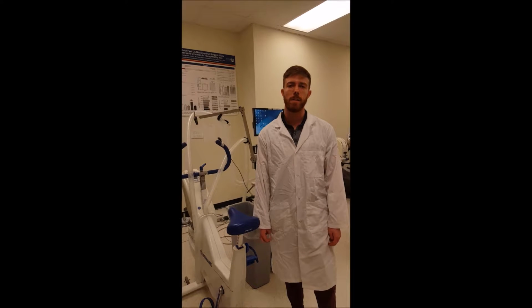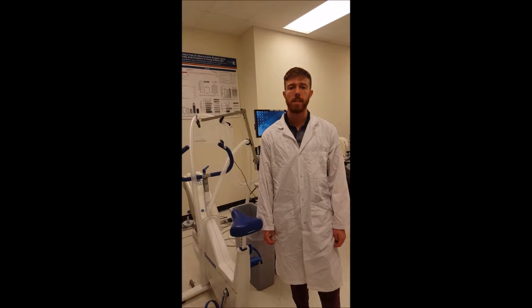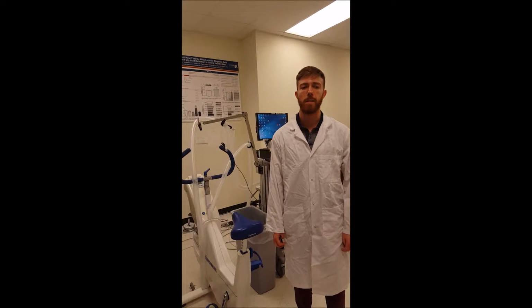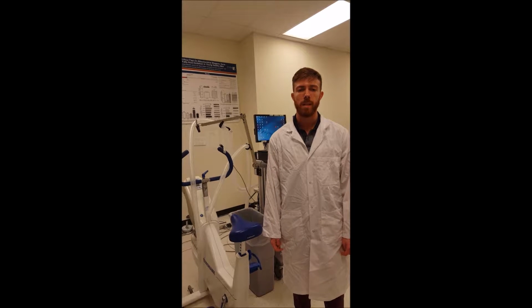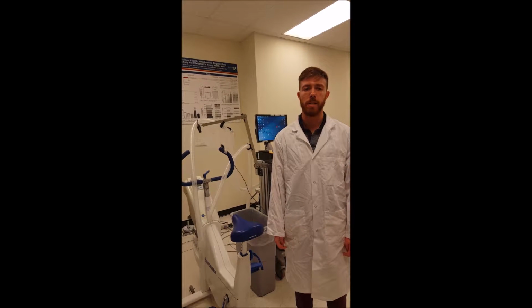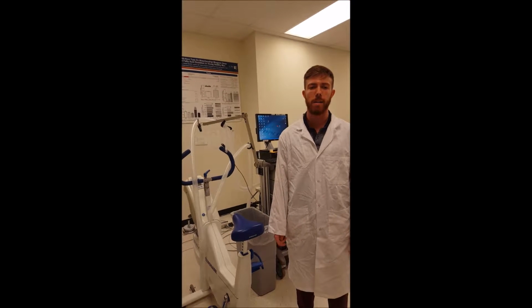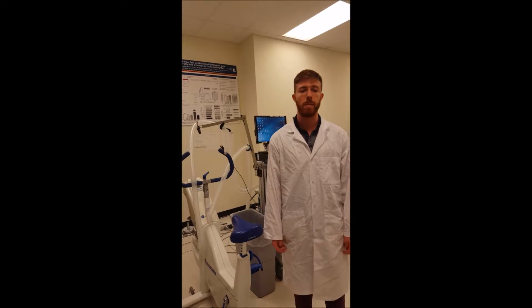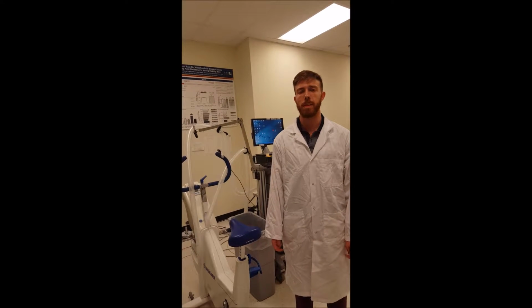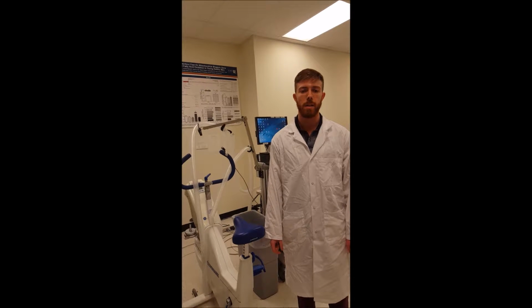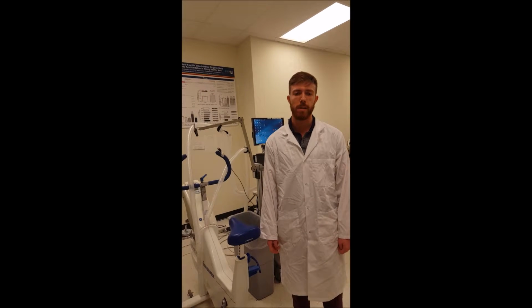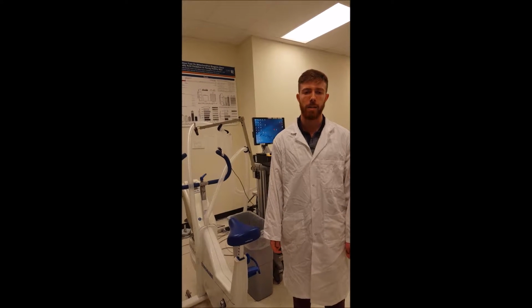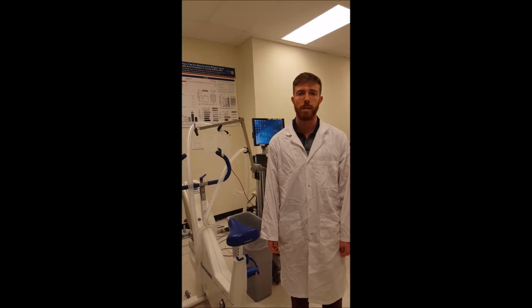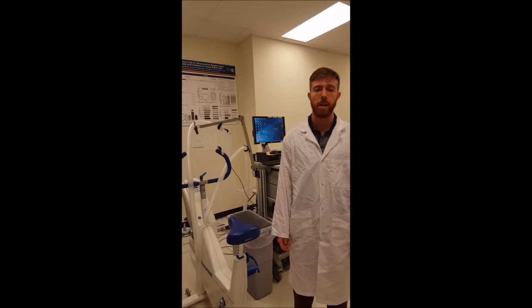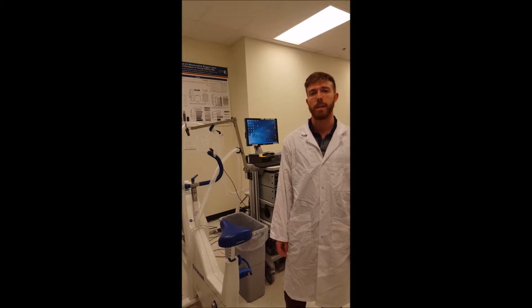The first step in using the system is calibration. Calibration is vital in order to obtain valid measures of gas exchange. Calibration shows the machine a standard or known value of gas, such as from the atmosphere or from a gas tank, which represents high O2 conditions. This allows the machine to have a reference for the measures that will be taken throughout the study. Calibration accounts for error and readjusts all values necessary to get the most accurate data.